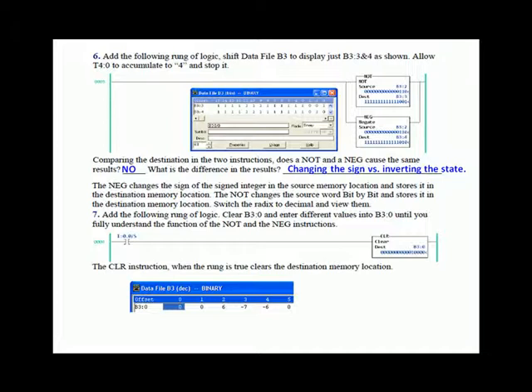The NOT instruction, if you look at B3:2 and B3:3 very closely, you'll see that all it does is change the bit pattern. If there's a 0 in B3:2, it changes it to a 1 in B3:3. If there's a 1 in B3:2, it changes it to a 0 in B3:3. Whereas the NEGATE instruction actually changes the sign of the value. If you look at the source versus destination in the NEGATE instruction, there seems to be no rhyme nor reason between the bit positions.